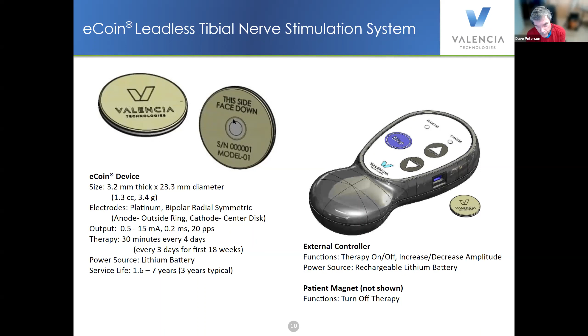There's also a patient magnet for this that's principally to turn off the therapy if there's a problem. We didn't want the patient going home and not being able to disable the therapy if there was a problem. But the external controller is really designed for clinician use, to turn it off and adjust the amplitudes. Oops. So this is sort of what it looks like inside the device.